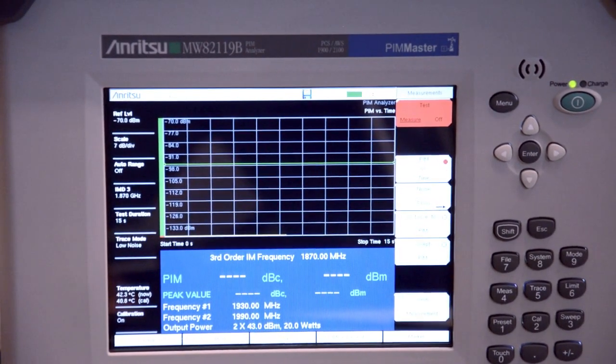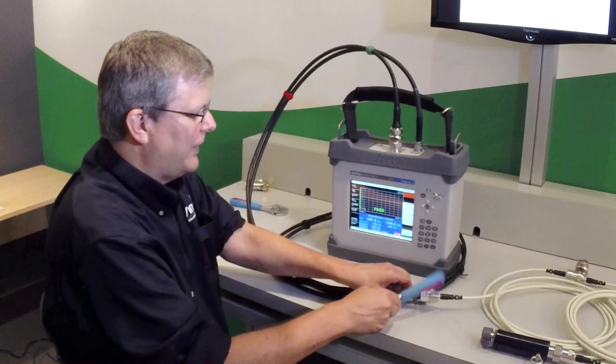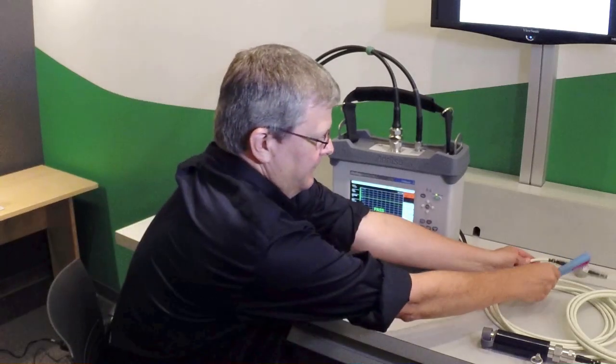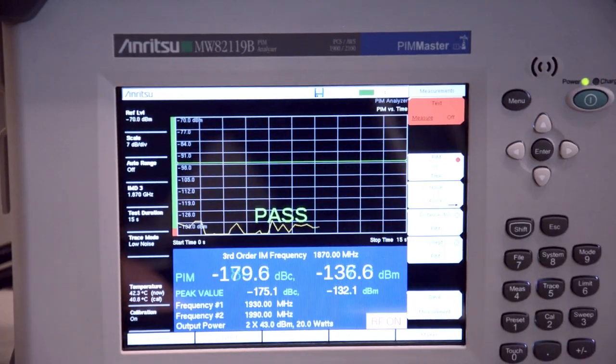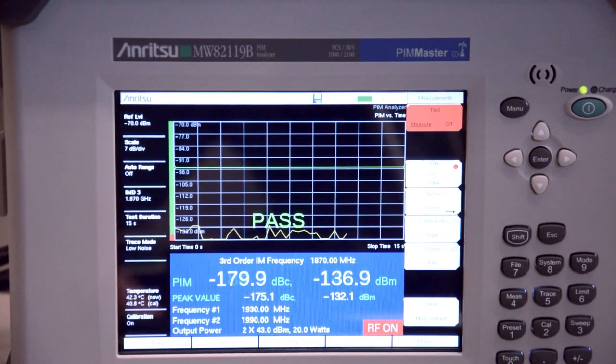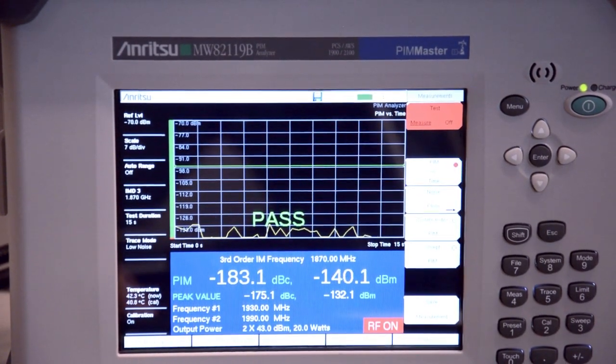I do my final PIM versus time measurement while tapping on the connections. We now see that we have a stable PIM measurement even when applying the dynamic testing. This is now a passing result.